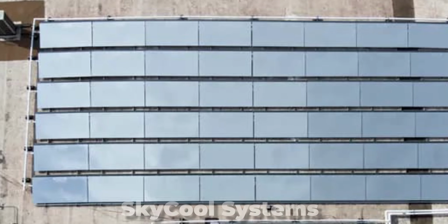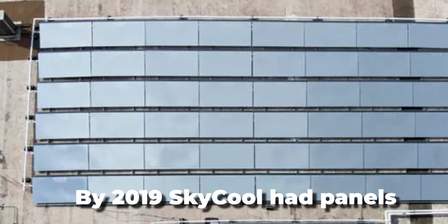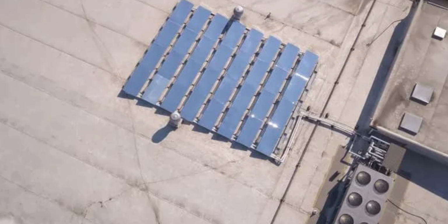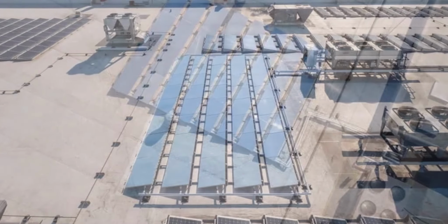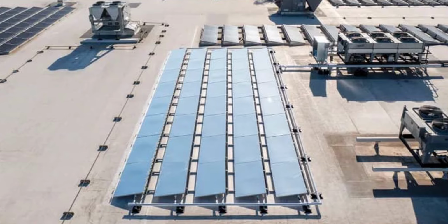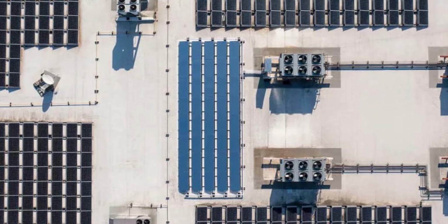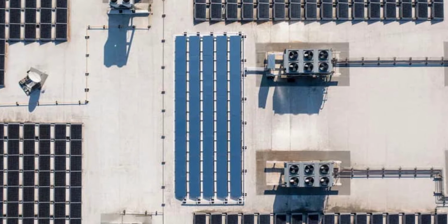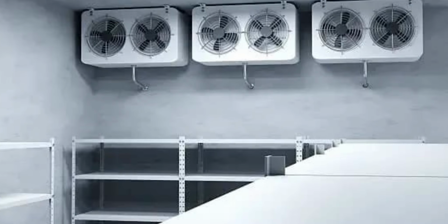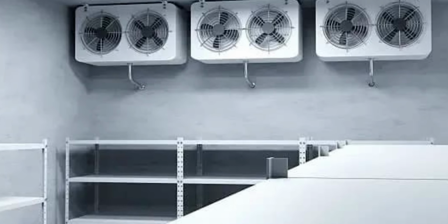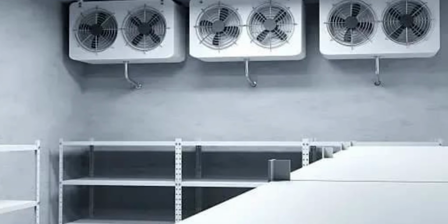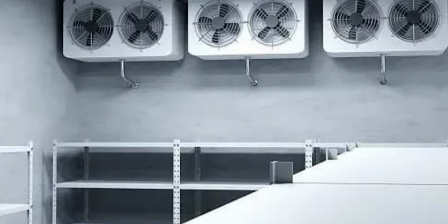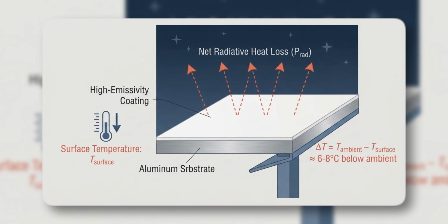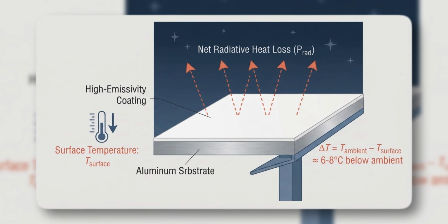One of Fawn's co-researchers, Aswath Raman, later co-founded a company called SkyCool Systems. By 2019, SkyCool had panels mounted on a grocery store roof in Stockton, California, pre-cooling refrigerant fluid before it hit the store's condenser units. Measured result, a 12 to 20% reduction in cooling electricity. For a grocery store, spending tens of thousands a year on refrigeration, that's thousands in annual savings from panels that draw 0 watts. Separately, researchers in Mendoza, Argentina, tested a much simpler version.